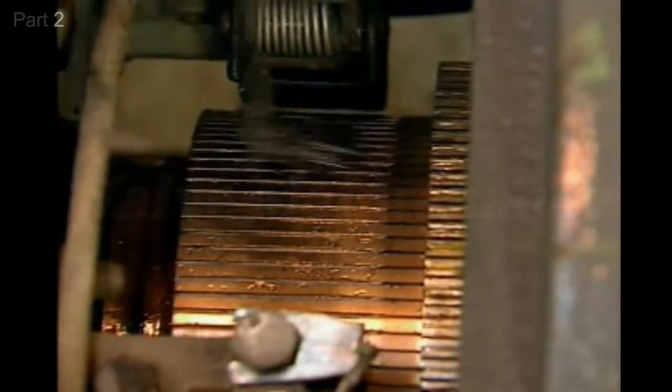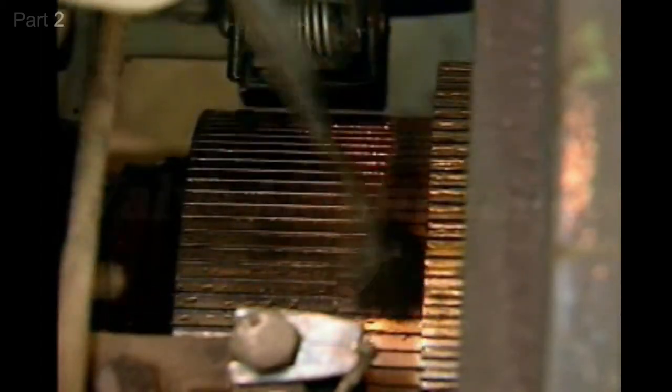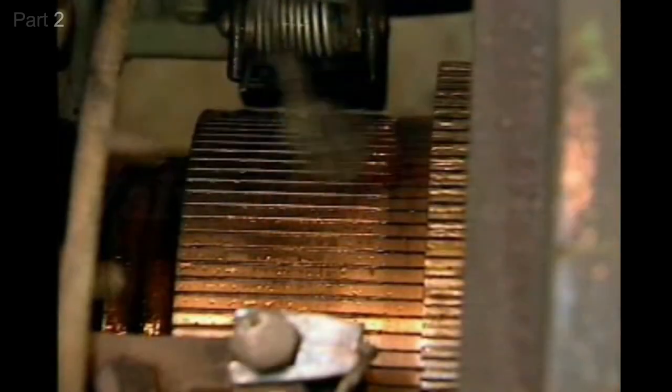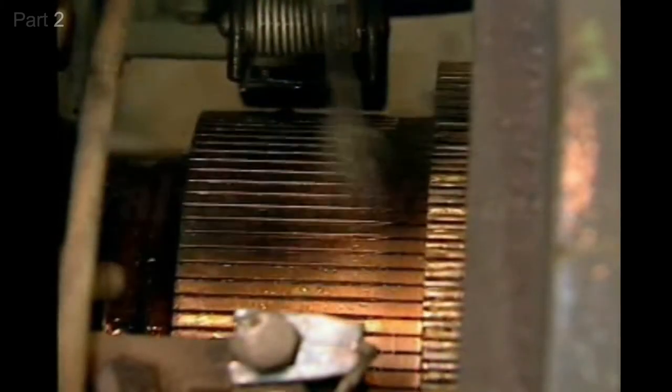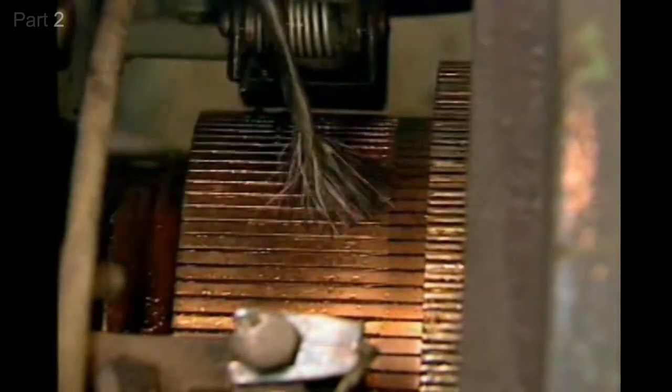Cleaning the commutator also involves cleaning the area between the segments. Care must be taken to ensure that the brown coating on the segments is not removed. This coating aids current flow between the brushes and the commutator when the motor is operating.